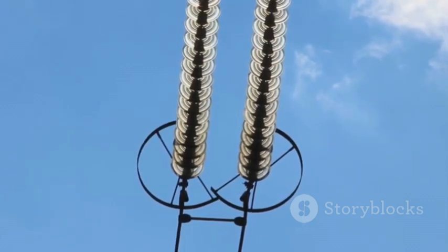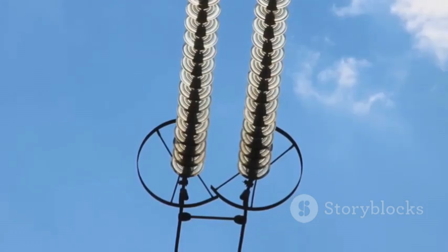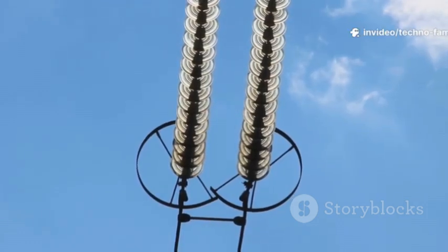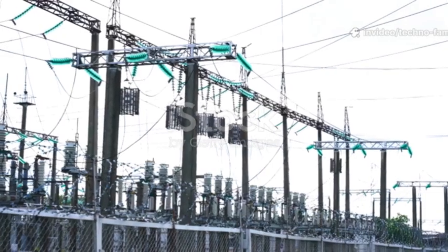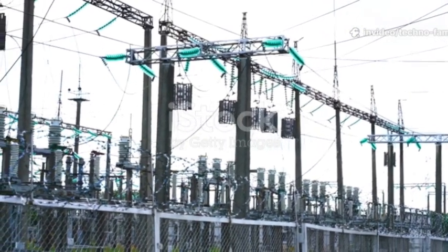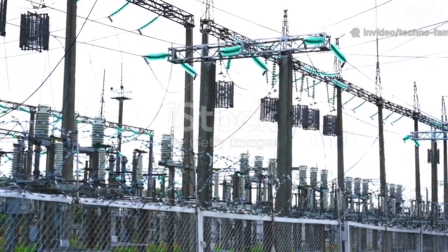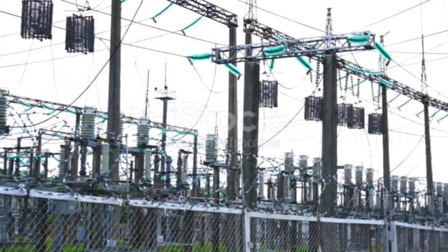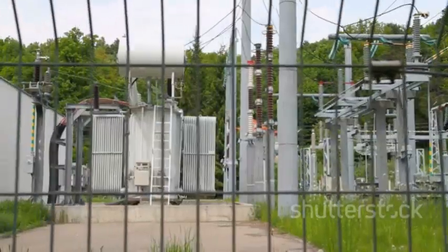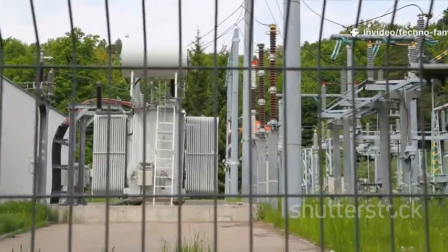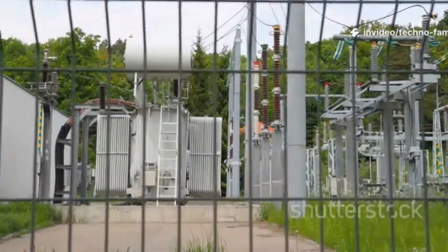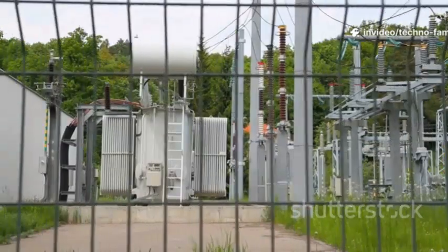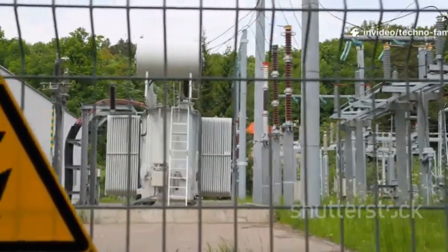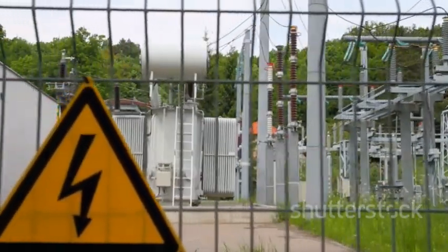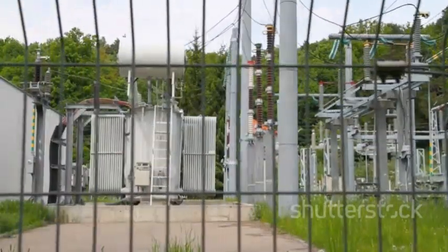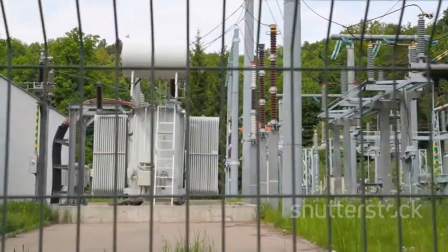Clean, dry, prevent contamination. Grading of insulation, for example, solid-liquid or solid-gas interfaces. Now that we understand the materials and physics, let's see how high voltage is used in real systems. Power generation to transmission: power is generated typically at medium or low voltage, for example, a few kV in power plants. To transmit large powers over long distances, voltage is stepped up using transformers to high or extra high voltages, tens or hundreds of kV.